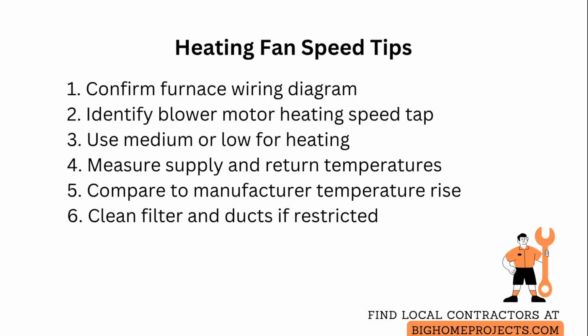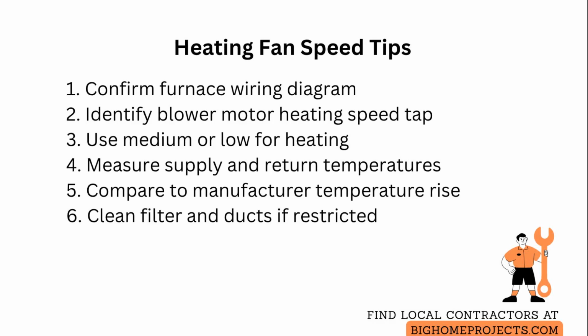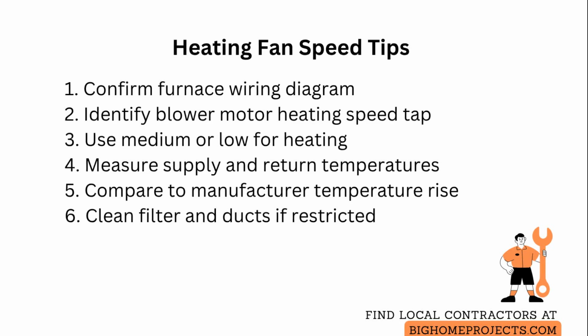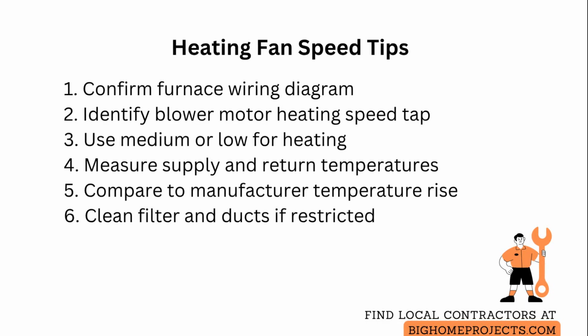Measure airflow and temperature rise with a thermometer at the supply and return vents, and compare the change to the manufacturer's specified temperature rise to verify the chosen speed is correct. If the measured rise is too low, decrease the fan speed or reduce airflow restrictions, such as a dirty filter or closed vents, to raise the temperature rise.